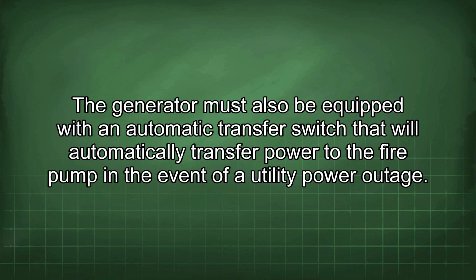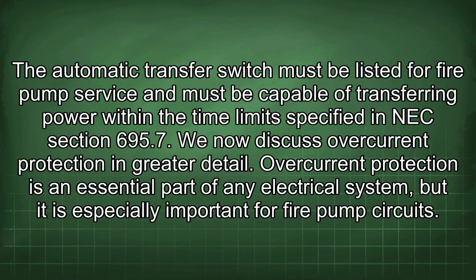The generator must also be equipped with an automatic transfer switch that will automatically transfer power to the fire pump in the event of a utility power outage. The automatic transfer switch must be listed for fire pump service and must be capable of transferring power within the time limit specified in NEC Section 695.7.